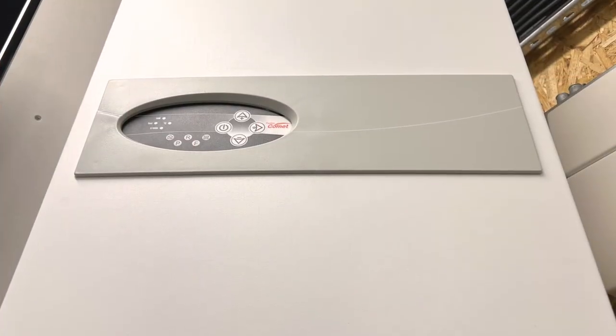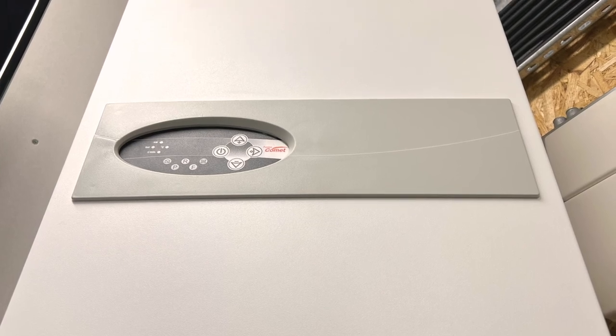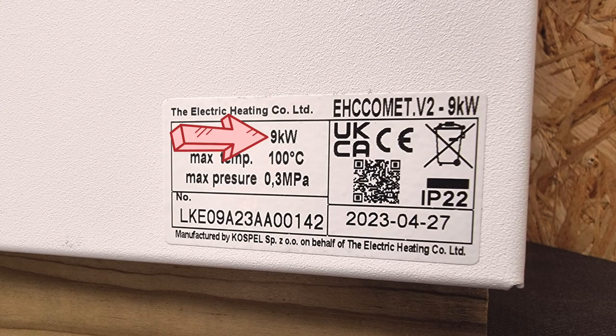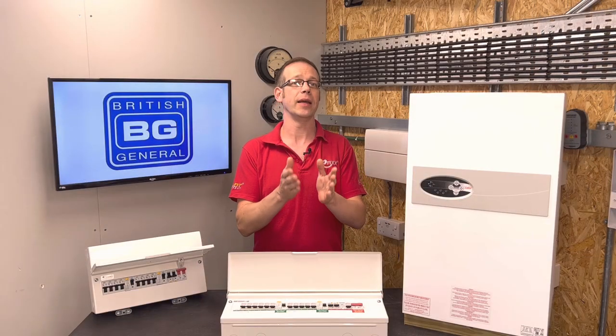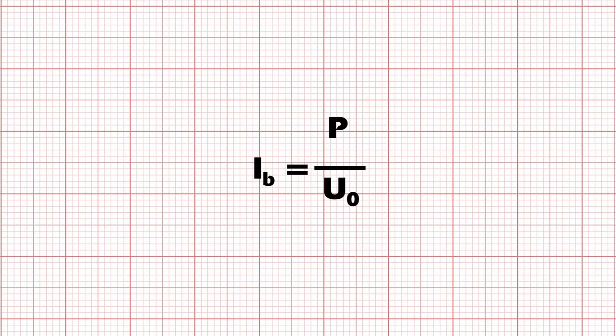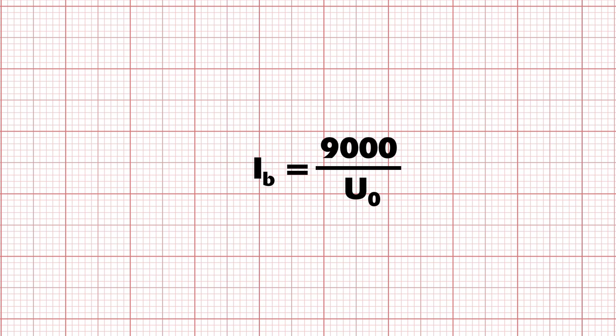So let's put our numbers in. We said this electric boiler has a rating of 9 kilowatts. Before we put this into our formula, we need to change kilowatts to watts by multiplying by 1000 — because kilo, that K, just means groups of 1000 — so that becomes 9000 watts. Pop 230 volts in at the bottom for nominal voltage, and we've got 9000 divided by 230, and that gives us 39.13 amps.